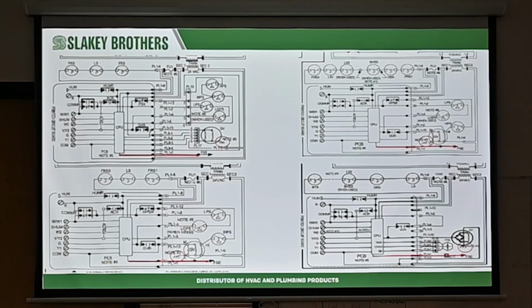As long as I confirm all that's good, I plug it in, and all the pins aren't damaged or nothing. It does sometimes happen. It could just be a faulty brand new unit circuit board, unfortunately. It does happen sometimes, but that's how you're going to determine: is it a bad switch? Is it not connected to the right spot? Is there something wrong with my inducer motor? Something wrong with my wiring? Or something wrong with my circuit board overall?